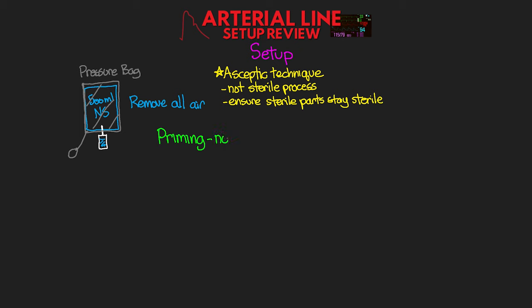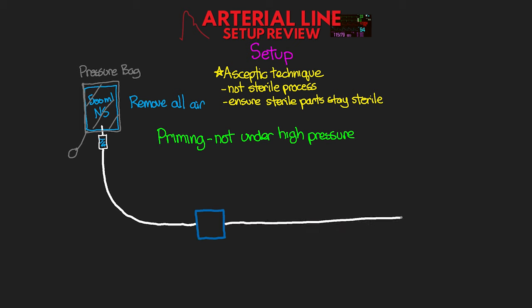It's really important that we do this not under high pressure, as this can actually damage the transducer. In order to do so, we want to make sure that our roller clamp just below the drip chamber is unclamped. And the first thing is we want to prime to the transducer and the zero point, which is going to be that three-way stopcock just below it. And so here we want to make sure that that stopcock is off towards the patient or the end of the tubing. This is going to allow a free flow of fluid down through the transducer and out the side port.